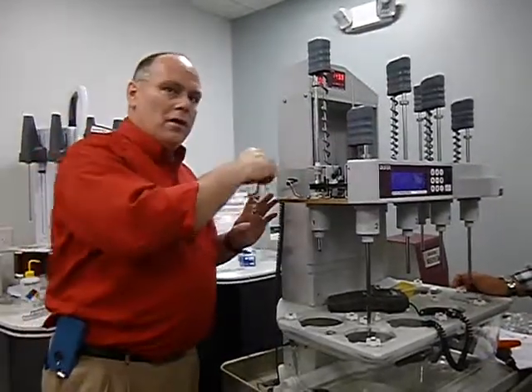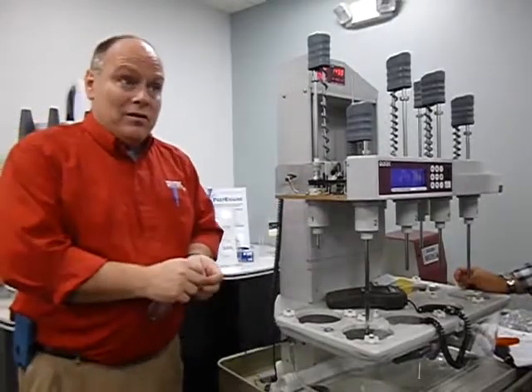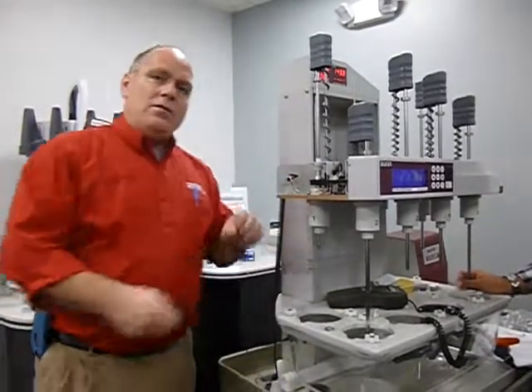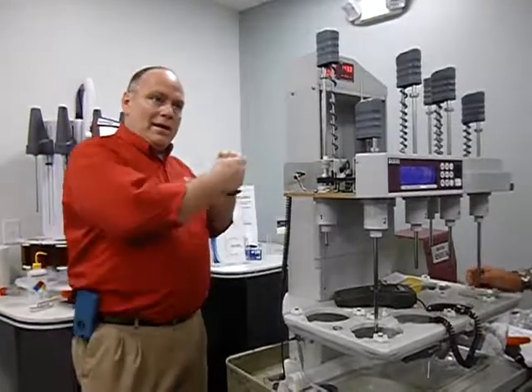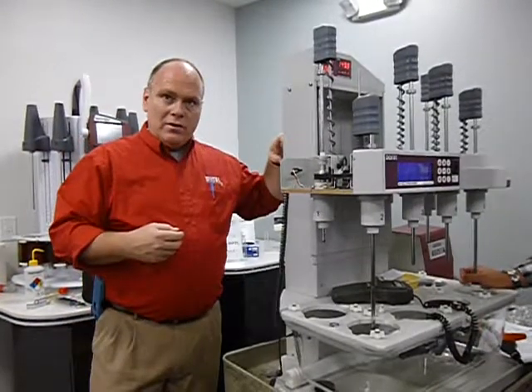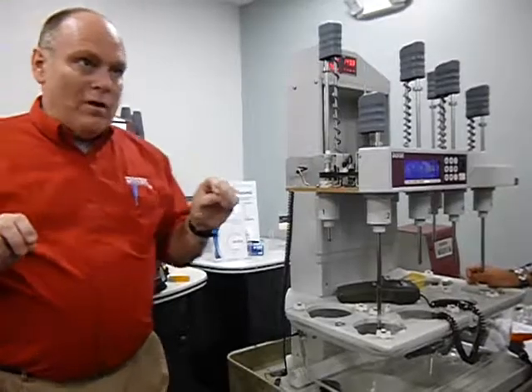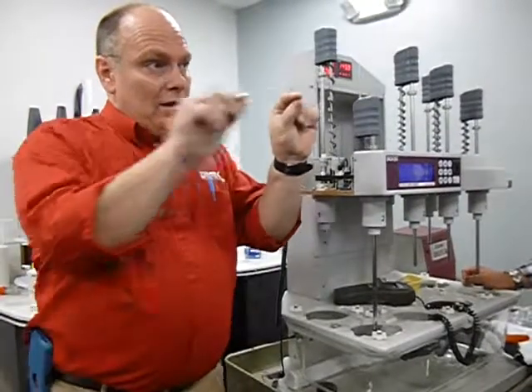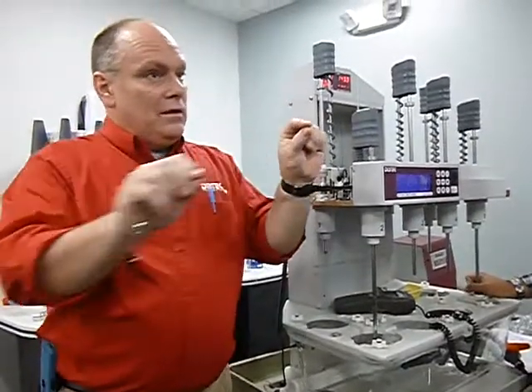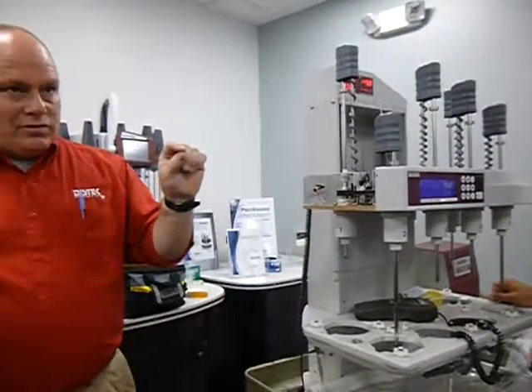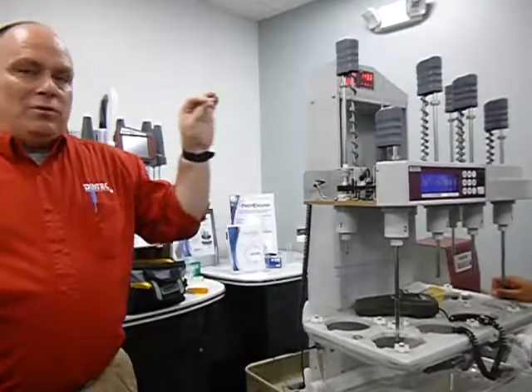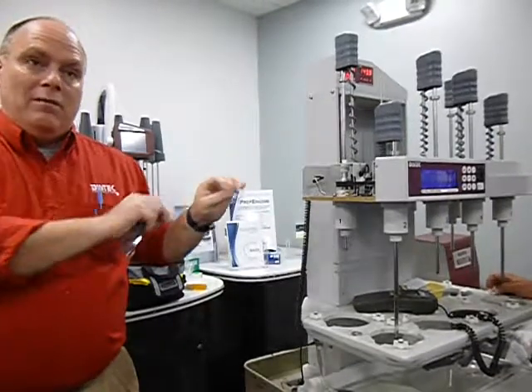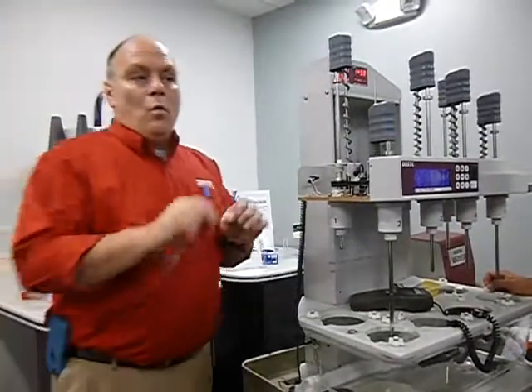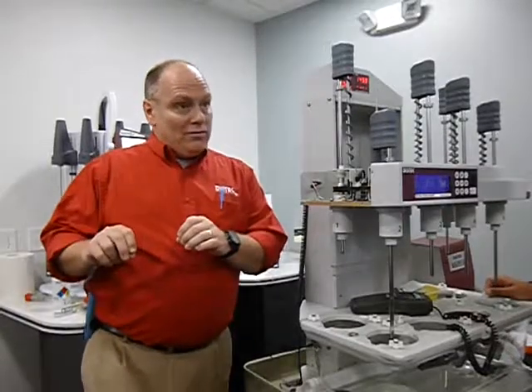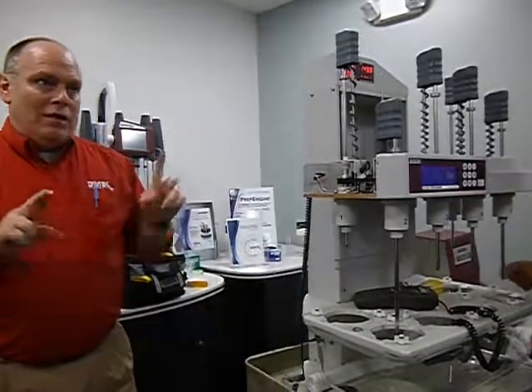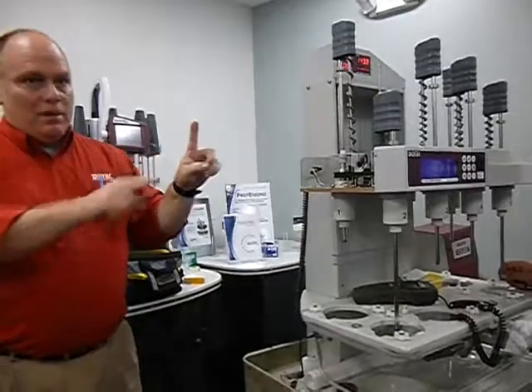When you plug in the number, you're telling it at that resistance, this is what the temperature is. And then you're doing the upper one at 40 degrees, and you're telling it at this resistance, it reads 40 degrees. That way the algorithm inside via programming can plot on a straight line exactly what the resistance should be, what the temperature should be at every single resistance. So all you're doing is you're giving it 2 resistant points of reference so that it can plot via programming. So again, that's why you need to do one around 20 degrees or less, and one at around 40 degrees. That way you have a nice linear line for it to plot everything on.